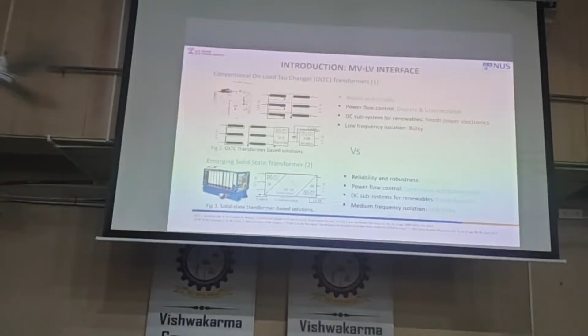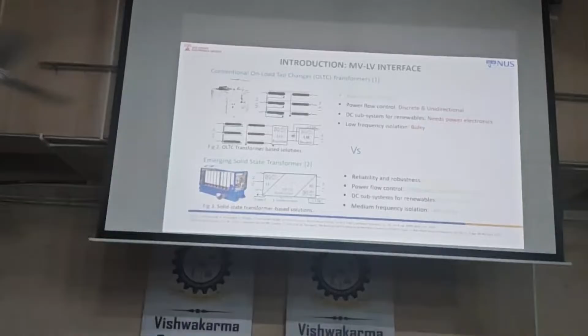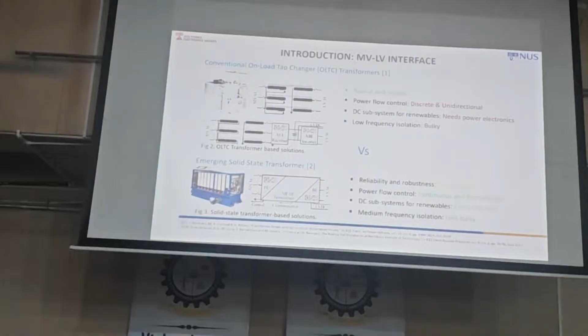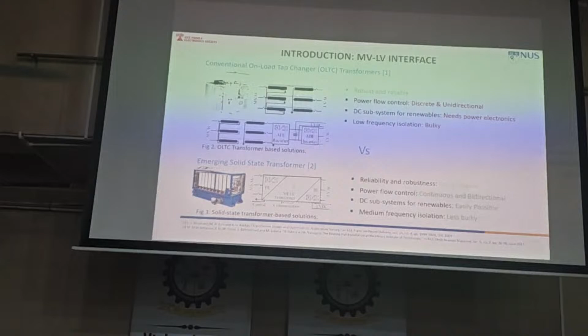This is called a solid state transformer. If I increase the frequency from 50 Hertz to 50 kilohertz, 1,000 times more, I can shrink the size of the transformer - not in the same ratio of 1,000 times, but in a non-linear way, about 10 times reduction in size and weight. That is why if I can reduce the size and weight of a transformer by 10 times, I can put it on top of the building.